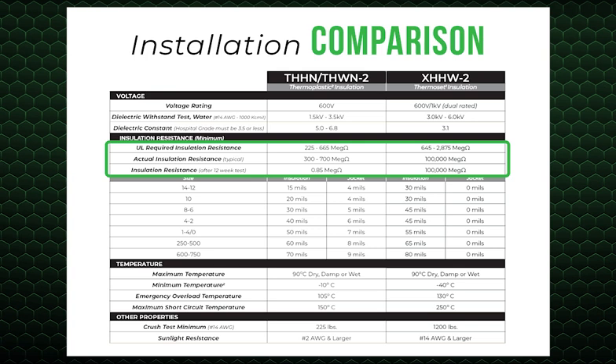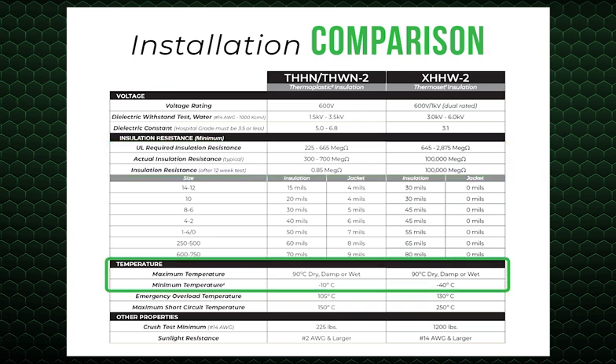The XLP insulation used in service wire's XHHW-2 has substantially higher insulation resistance, greater overall electrical insulating properties, and withstands much higher voltage spikes than THHN. Extreme cold temperatures can have adverse effects on wire and cable, causing them to become brittle and inflexible. This can lead to cable damage and safety risks. Service wire's XLPE used in XHHW-2 is cold temperature rated at negative 40 degrees Celsius. The cold temperature resistant polymer helps the cable maintain its flexibility during cold weather installations.